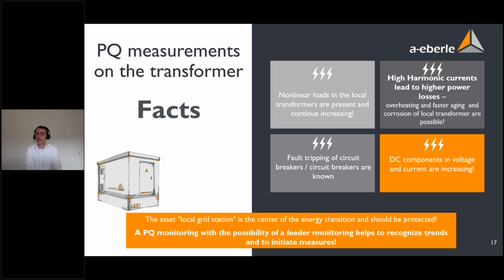Non-linear loads in the local transformers are present and are continuing to increase. Fault tripping of circuit breakers are present and known. We have more harmonics in currents, and they are ending at more power losses. So we have overheating, faster aging, and corrosion of local transformers. They are possible. We can see that in the industry grids because the industry is much faster than we in the utilities. Also, DC components in voltage and current are increasing due to new technologies. So we have always an AC with a small DC on that, which ends in corrosion, which could be seen at the local transformer stations.